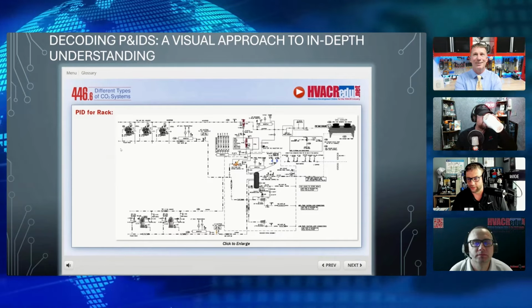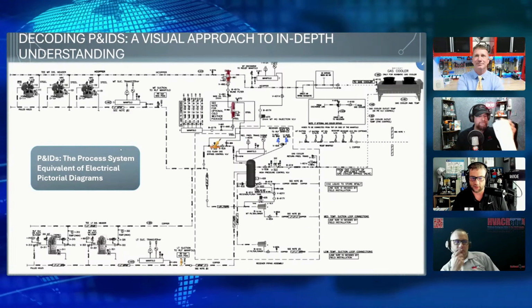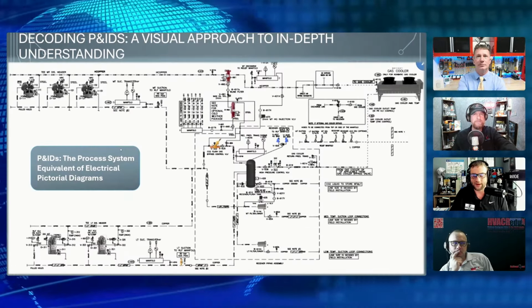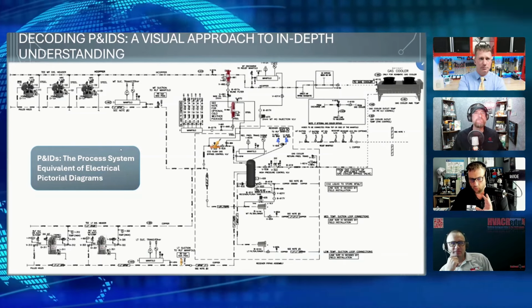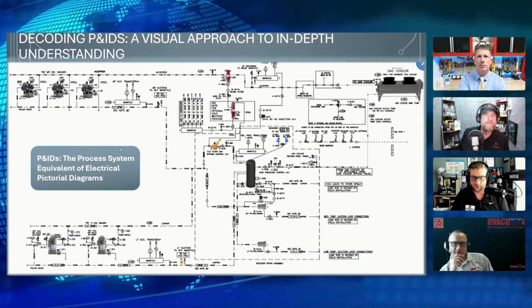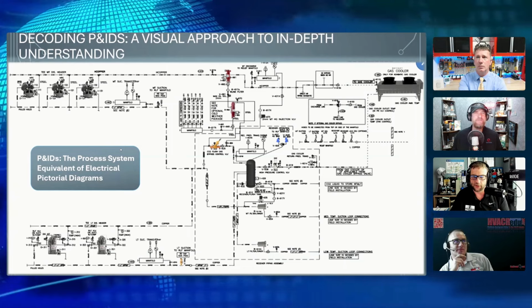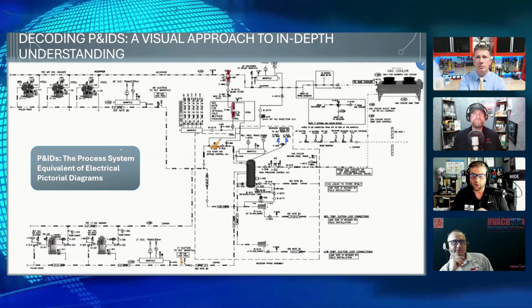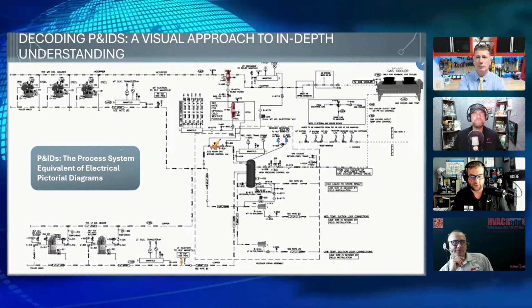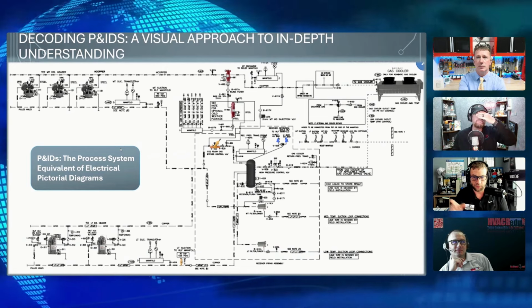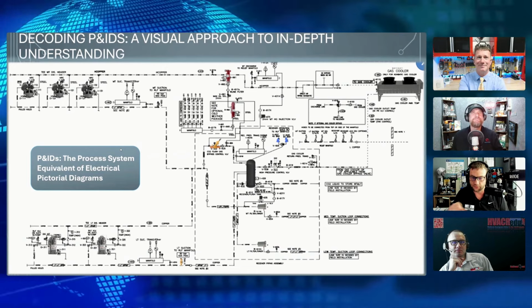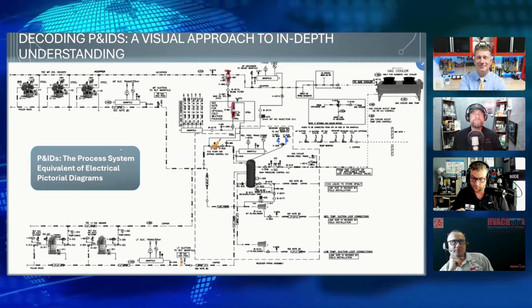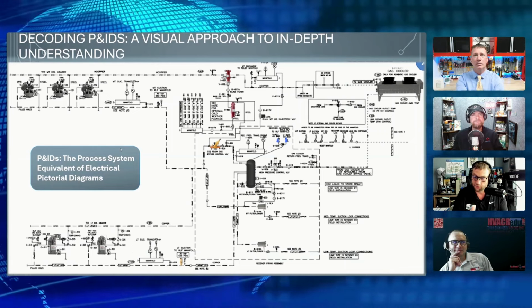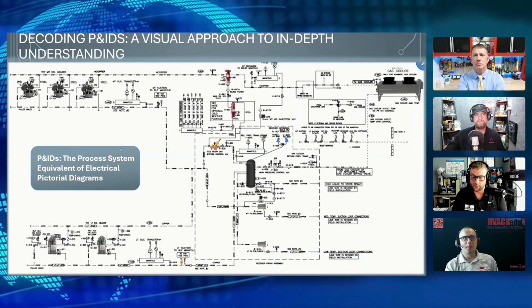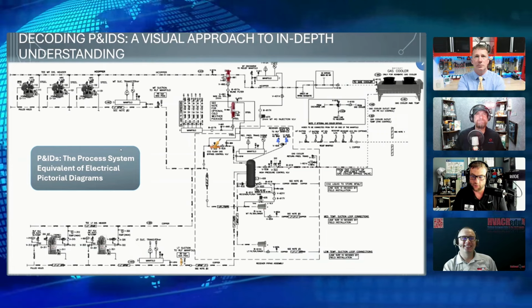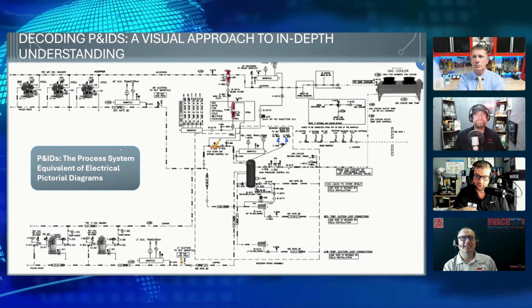I simplified it. There we go. I basically broke down every single component. Not every single component, but most of the most important ones. I'm not going to put every single ball valve on here. The oil separator, what it is. And usually when I teach, we don't even look at the rack first. We go through the components, we look through the sequence of operation, talking about the startup procedure and how it goes. Then we'll run through the sequence of operation through a P&ID diagram, but usually they don't look this pretty, so they don't have all these components. So what's the line with the squiggly thing with the S?